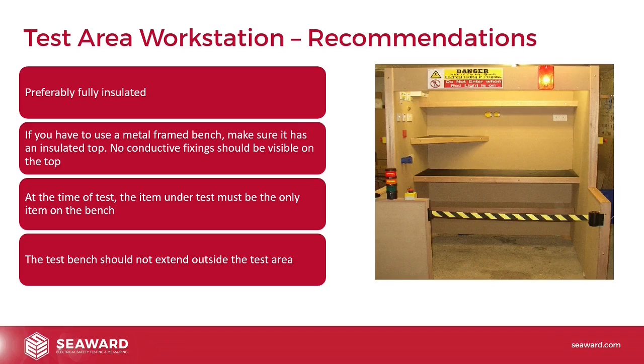So we'll start with the test area workstation and the recommendations that the standards make for those. They recommend that it's fully insulated, so ideally you want something made of wood, rubber, or plastic, such as that image in the photo there. If you have to use a metal framed bench, so it might be wooden topped with a metal frame, make sure that it has an insulated top. So if you are using a metal bench, have wood or rubber on top, something insulated. And no conductive fixings should be visible on the top.